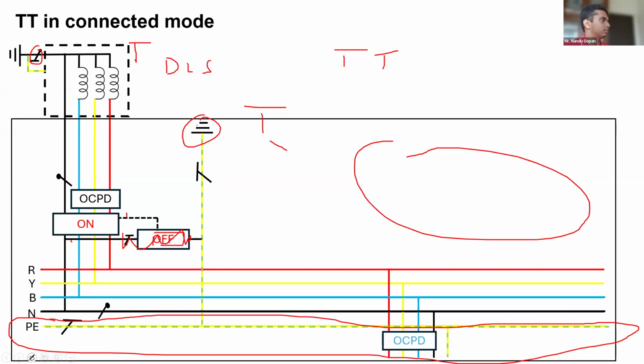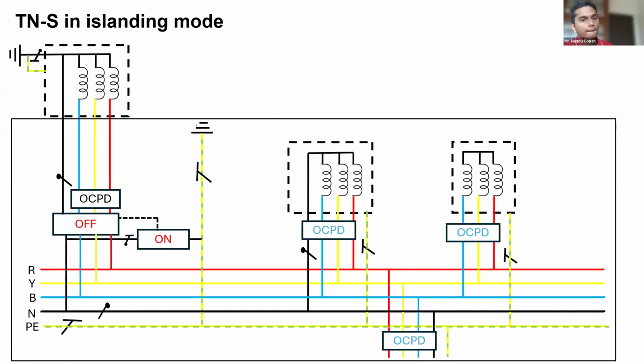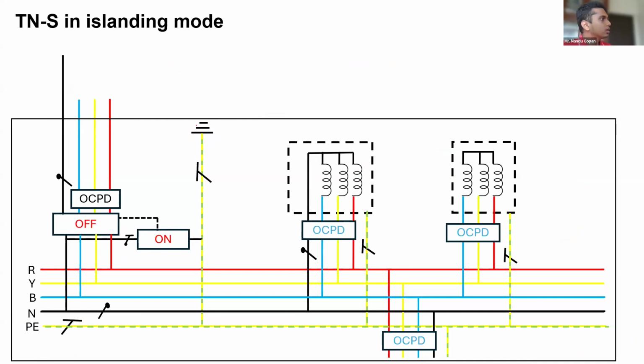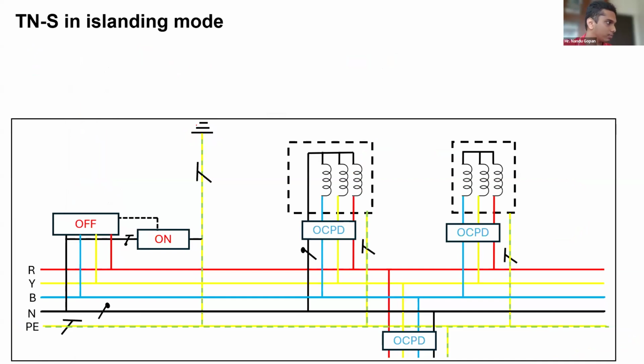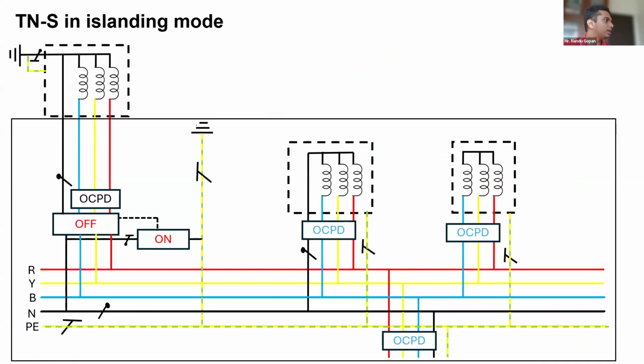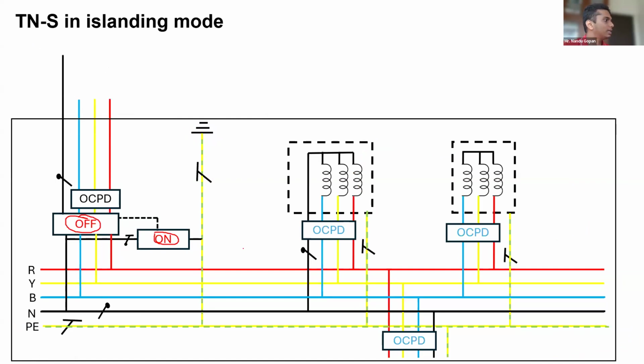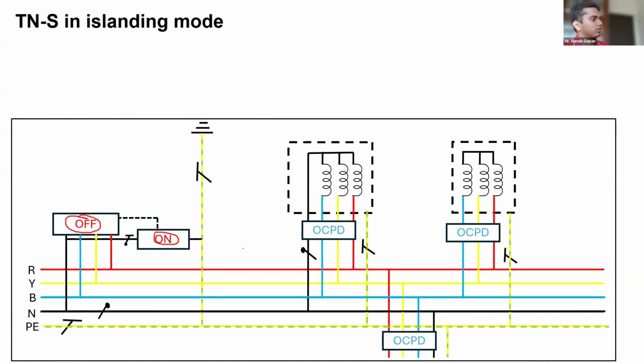So TT system. Now in this case, how do we change it to a TNS supply in case of islanding mode? So in islanding mode, you can take these things out. In islanding mode, this will be off. This switching device will be off, and this switching device will be on. So I'll take these things out. The discom transformer, I'll take it out.